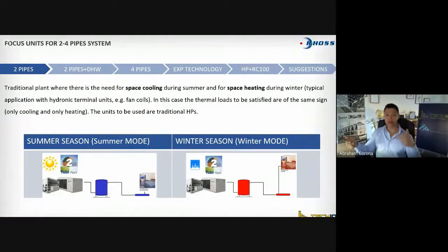We call it 2-pipe. Say we are in summer mode, and we're producing chilled water, maybe 12 to 7, standard condition in the Australian industry. You have an inlet connection and one outlet connection, so you have a 2-pipe system. We use that for air conditioning during summer, and use that for heating during the winter, all right? But this is where it gets confused. We say, okay, I'm going to count only the pipe connections, the water, hydronic connections that I made to my system, and I can define that I have a 2-pipe system. Yes and no, that's the correct answer to that.